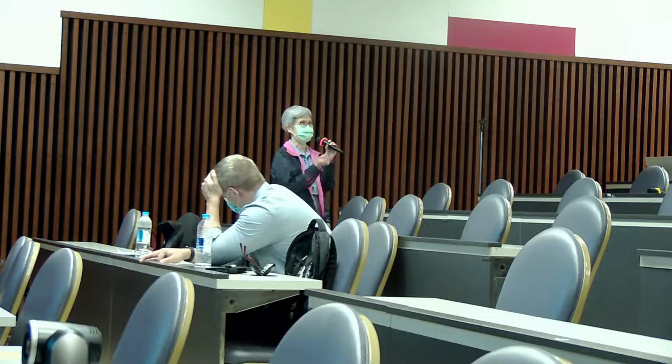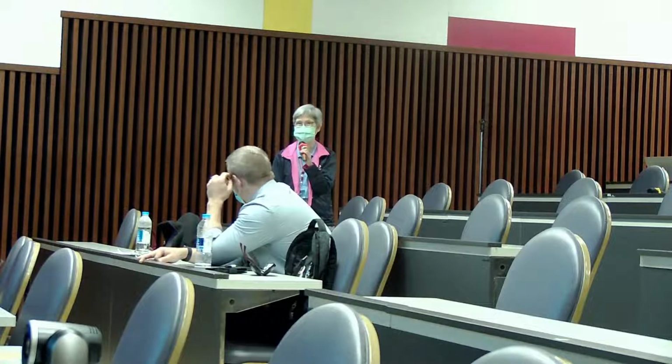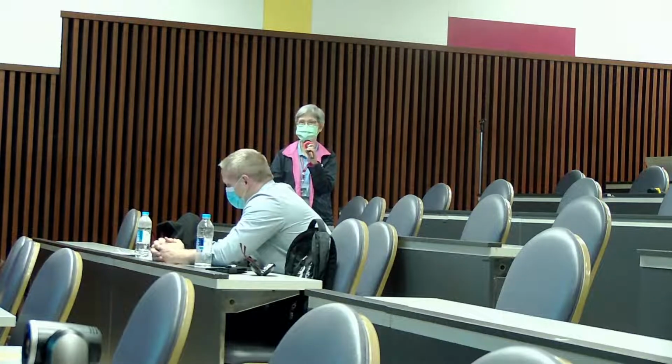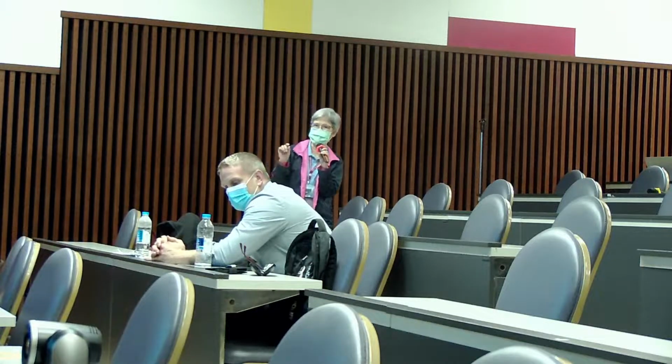And if we ask the CT technologists in general, they also don't know. They ask doctors how much the dose you want to lower, and they will change the mAs or the kV, and we look at that together. That's a problem, and we can ask the CT vendor to come in also and ask to lower the dose. That is the way that we set the protocols.